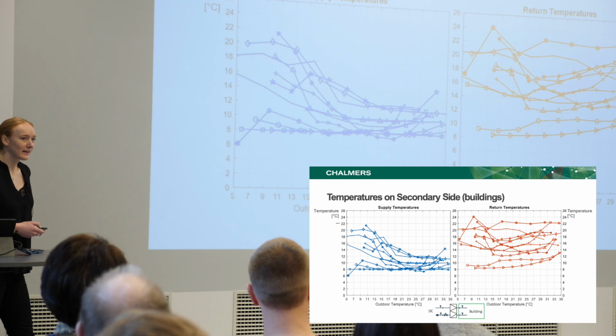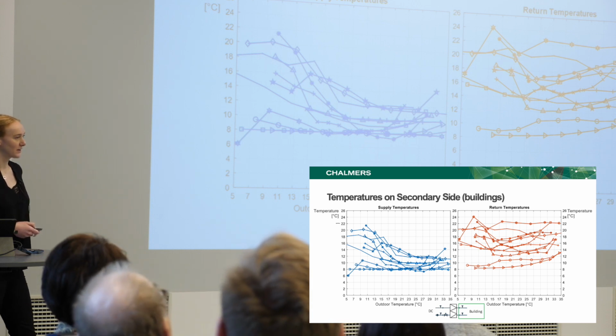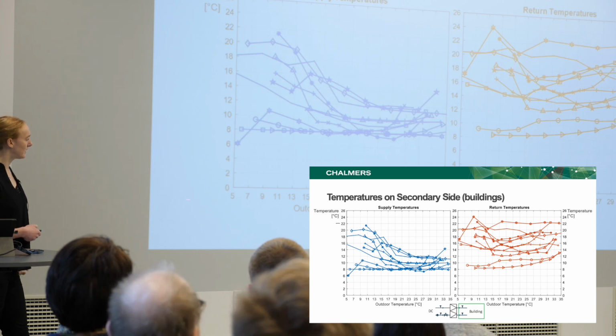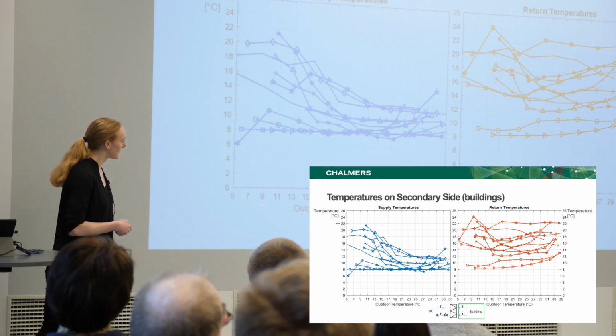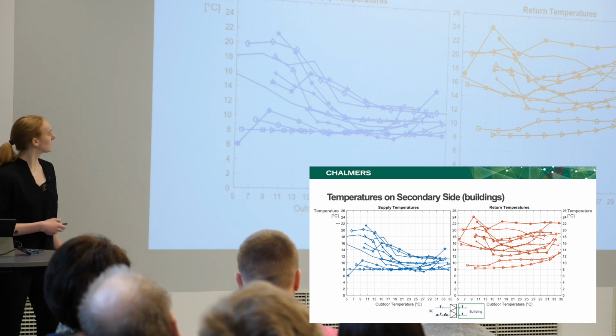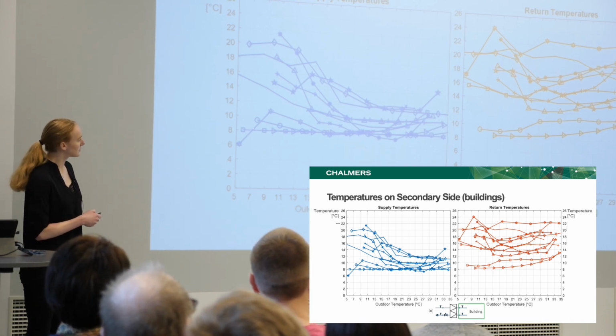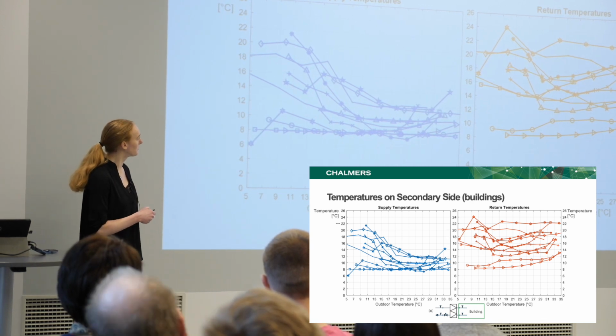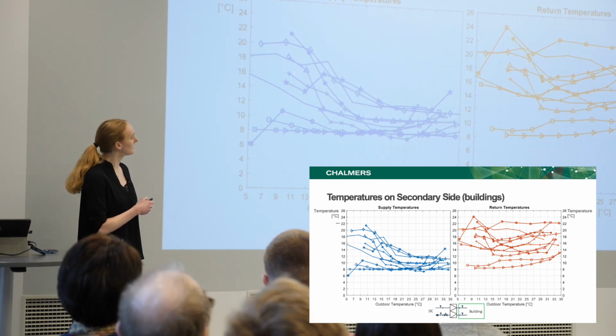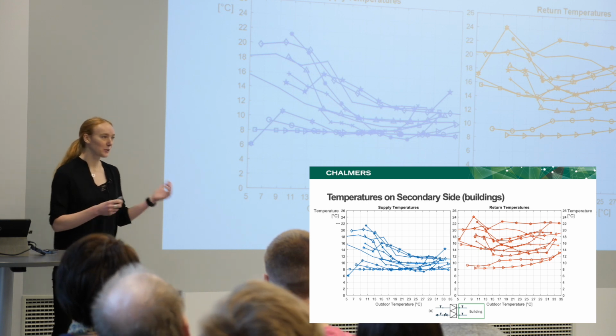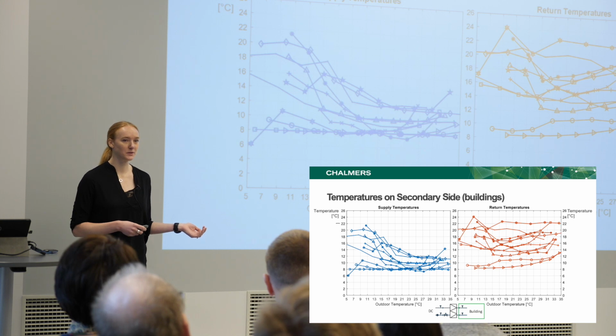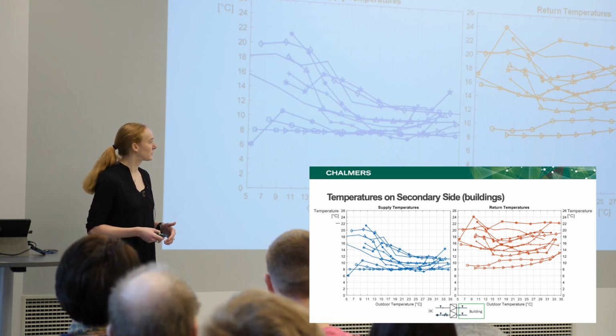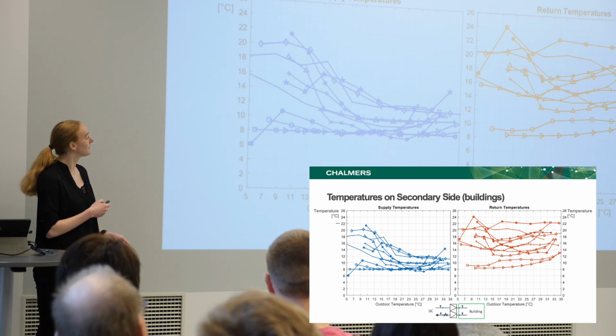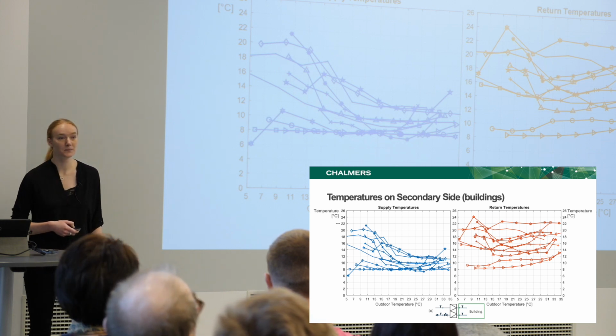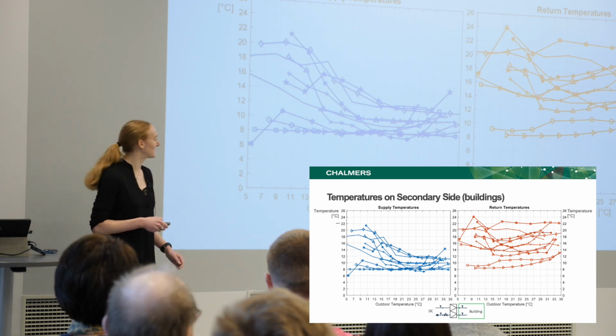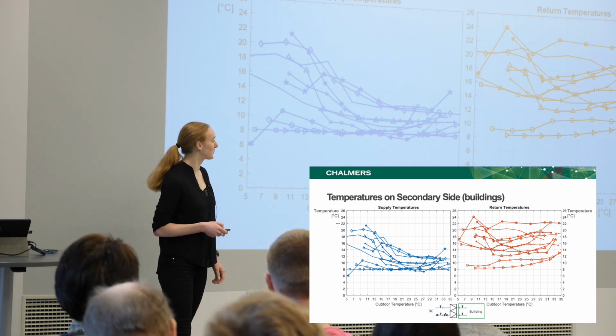Here you have a compilation of 12 buildings that have both supply and return temperatures available. What you have here on the x-axis is the outdoor temperature. What's interesting here is that not all buildings have set the supply temperature to 8 degrees, regardless of outdoor, but a lot of the buildings actually have this curve. So the outdoor temperature compensates the supply temperatures, just like on the heating side. The temperature is high when it's colder outside, and it drops lower when it gets warmer. So they don't use 8 degrees all the time, regardless of the outdoor temperature.